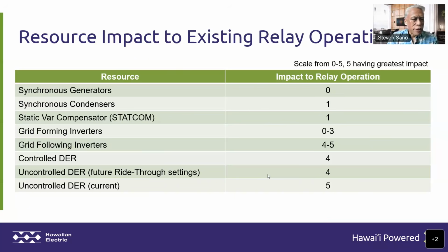But if instead we add things like synchronous condensers, which are similar to synchronous generators, the impact to relay operation is minimal. So again, on this subjective rating scale, we have 0 to 5, with 5 being the worst. Synchronous condensers are about a 1. Static VAR compensators, StatComs, again, sort of a similar thing. Impact would be a 1.